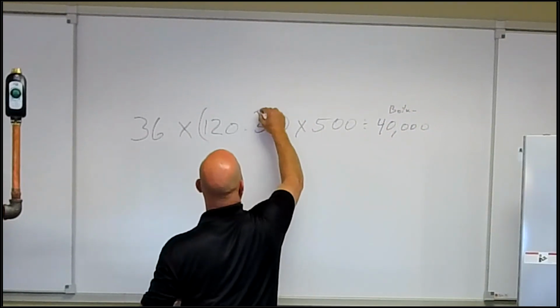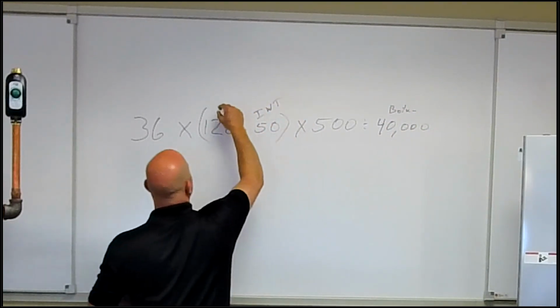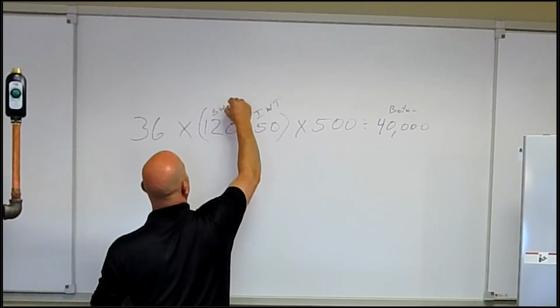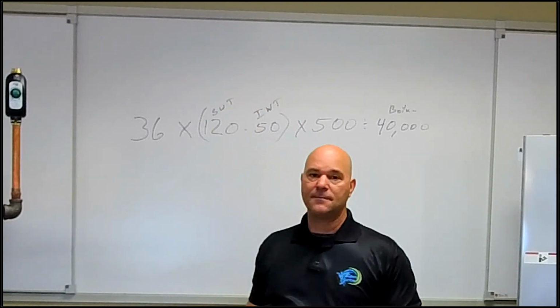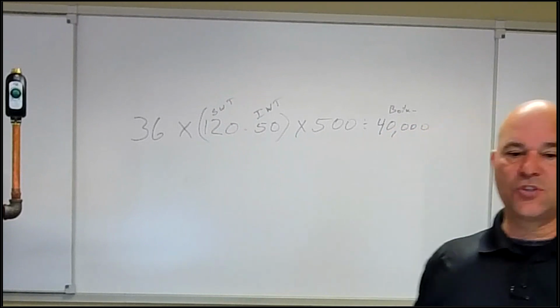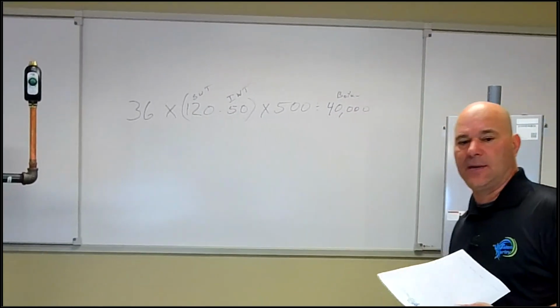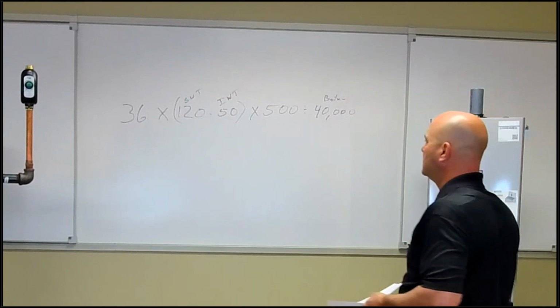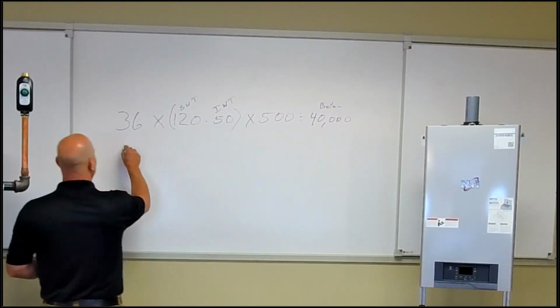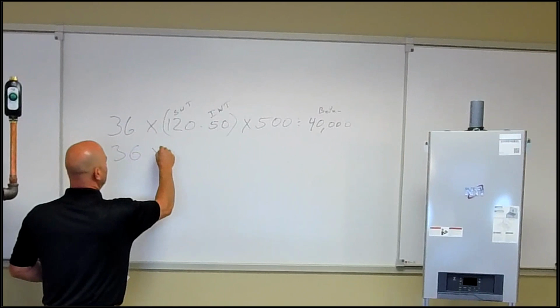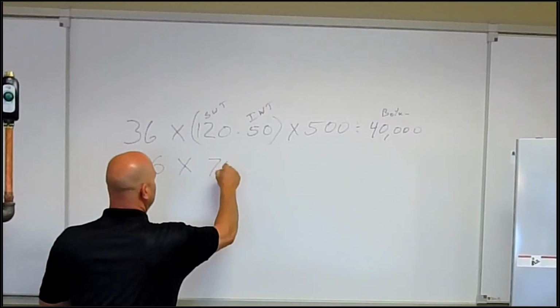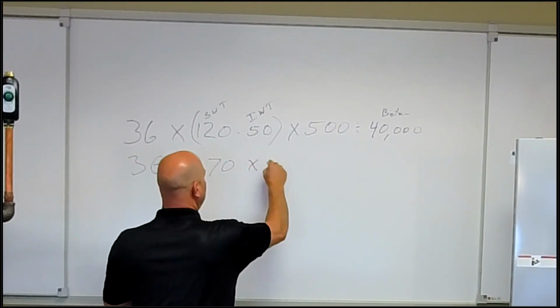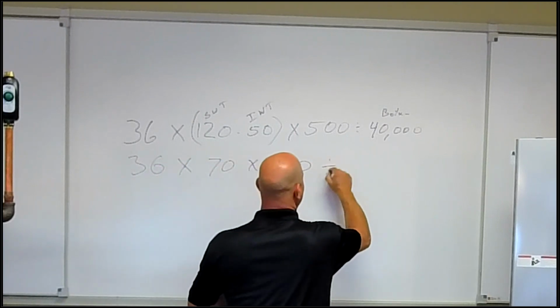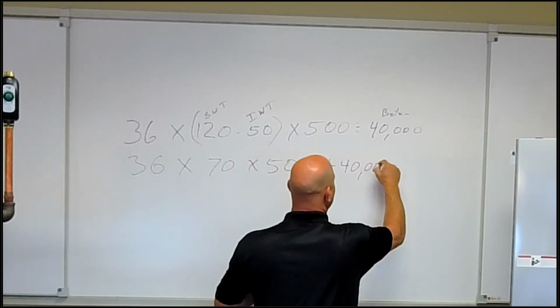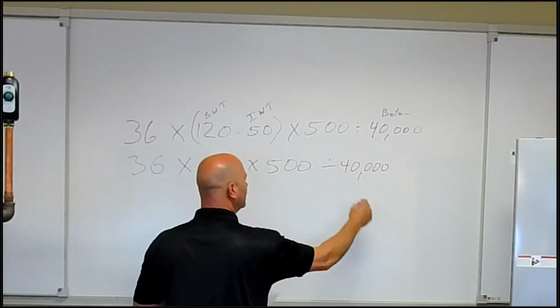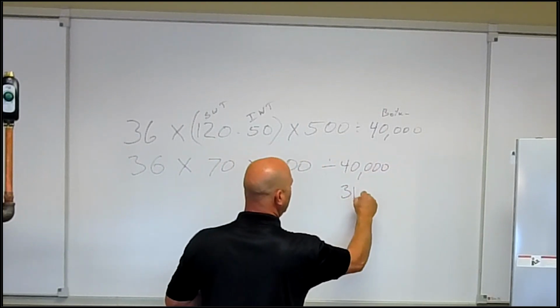This is incoming water temp. This is supply water temp. Okay? So somebody shoot Jim the answer. What's the difference between my 120 and 50? They all got the right answer. So it would look like this: 36 times 70 times 500 divided by 40,000. What's my answer, Jim? 31.5 minutes.